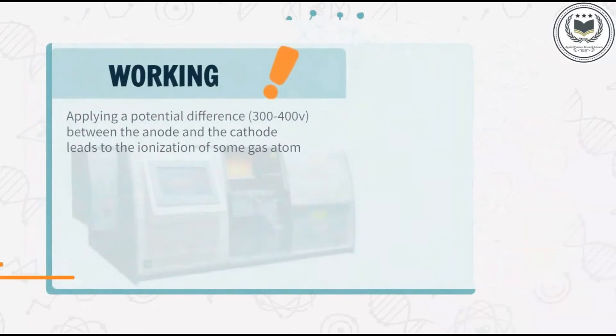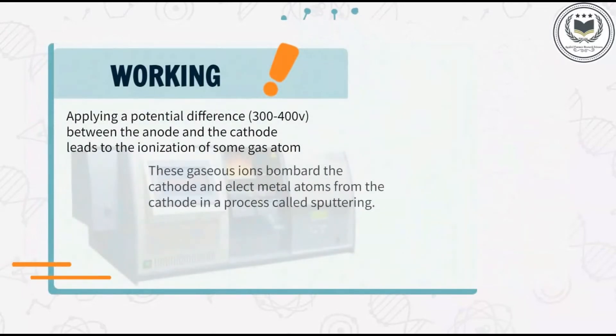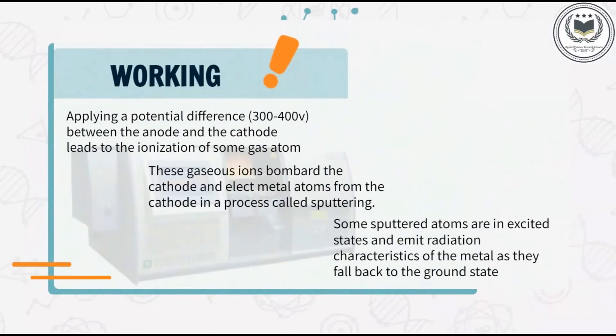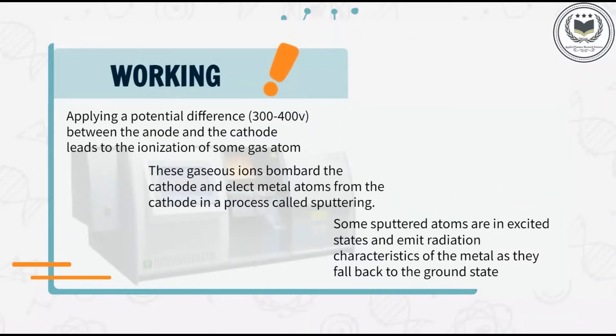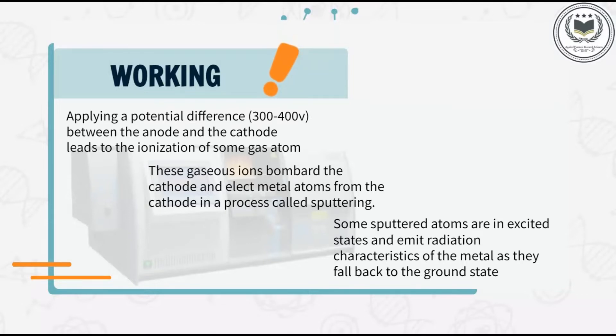Applying a potential difference of 300–400V between the anode and the cathode leads to the ionization of some gas atoms. These gaseous ions bombard the cathode and eject metal atoms from the cathode in a process called sputtering. Some sputtered atoms are in excited states and emit radiation characteristic of the metal as they fall back to the ground state.